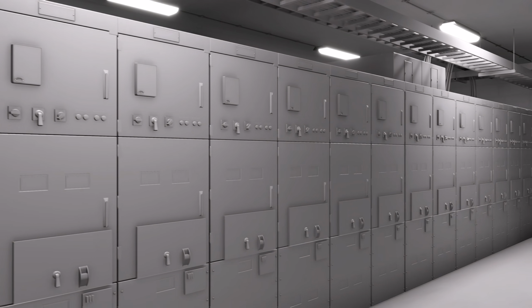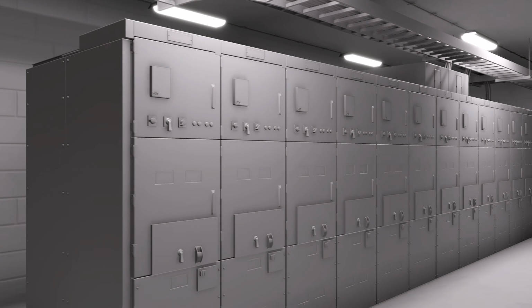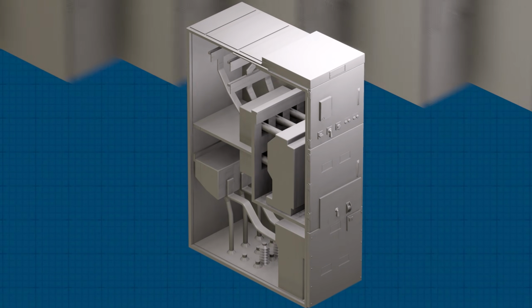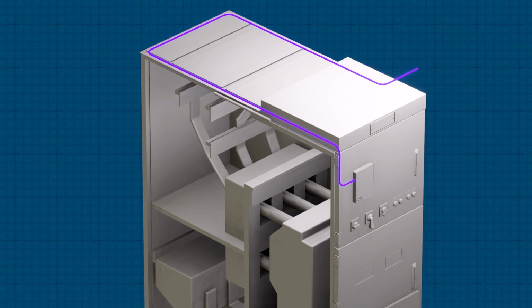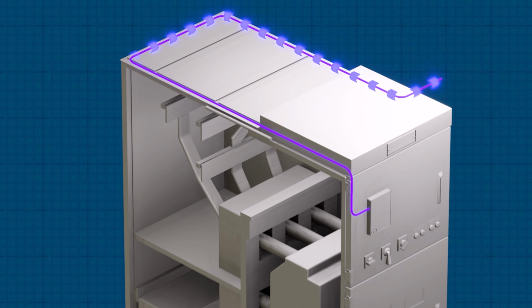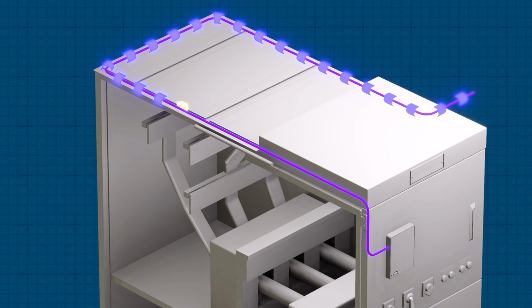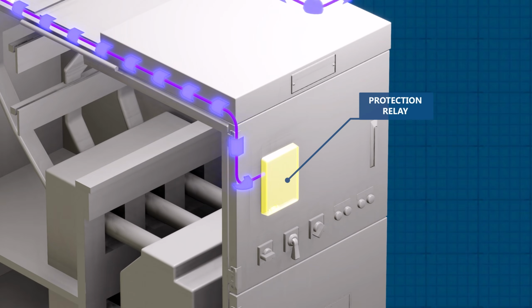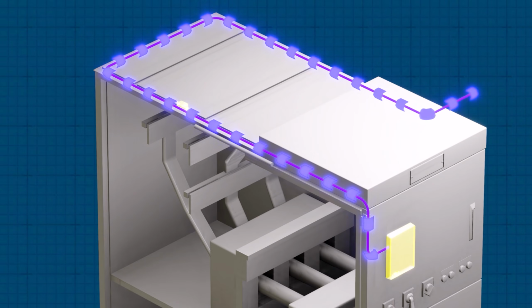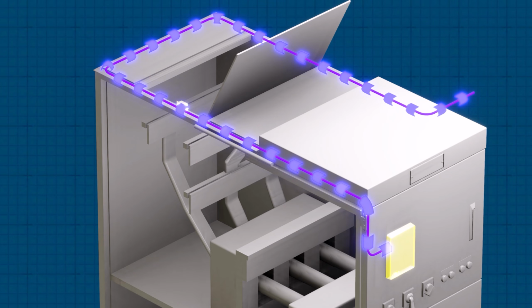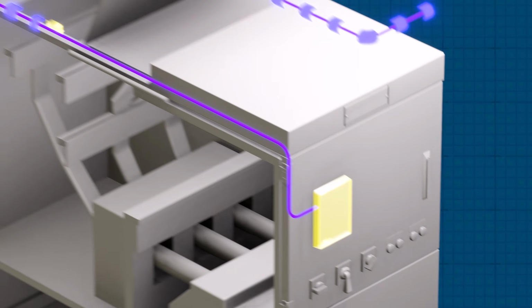A major hazard with high-voltage electrical systems is the occurrence of an electrical arc flash, an explosion caused by electricity passing through the air. When this occurs, it is critical to shut down the power source to prevent continued arcing and further damage to equipment. The system used to protect against arcing in Unit C4's high-voltage AC cabinets is called arc flap protection. The arc flap protection works by applying a DC voltage to a switch at the top of the cabinet. The presence of this voltage is monitored by a protection relay. If an arc occurs in the cabinet, the explosive pressure will blow open a flap on the top. When the flap opens, it opens the switch, collapsing the DC voltage to the relay.